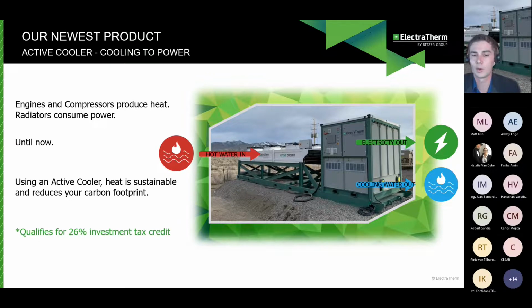And we are also always on cooling. So if the unit is not producing power, maybe you have a site that runs at a partial load, running at 50% load, and maybe it's a smaller engine that doesn't have quite enough heat for power production, we would still be able to cool that engine and maintain operation, because first and foremost, the main goal of our active cooler in any Power Plus system is to not interrupt operation. So it is always on cooling.